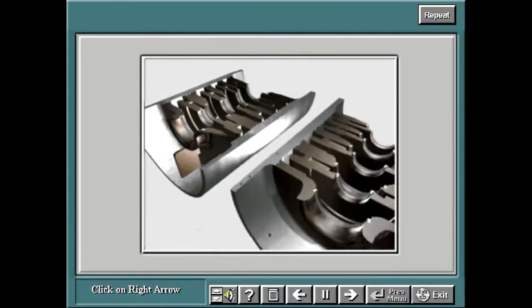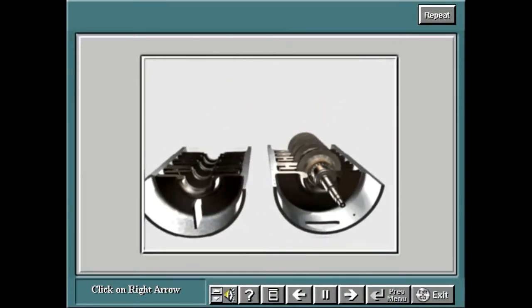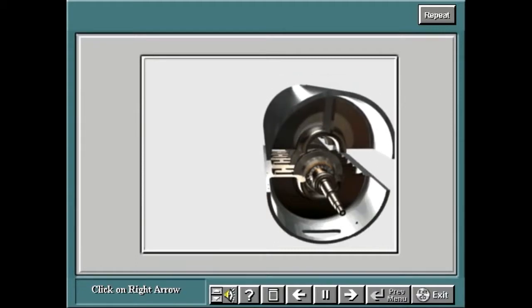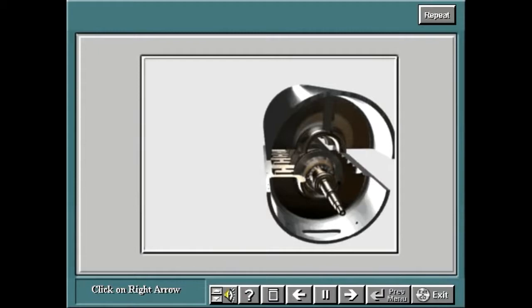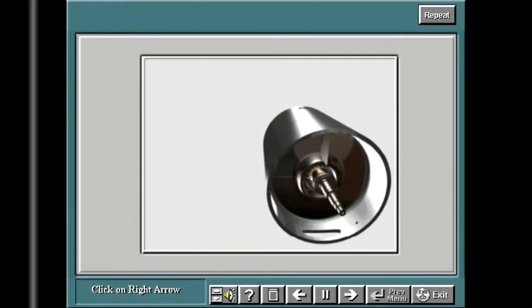The rotor assembly is inserted on the lower half diaphragms and rests on the lower half labyrinth seals. Then the axial position of the rotor is set and recorded. Next, the upper half of the counter casing is placed on top of the installed rotor and lower counter casing half. Before closing the counter casing halves together, O-ring segments, coated with lubricating grease, are fitted into position on the middle split plane of the lower diaphragm to minimize leakage between compression stages. Great care must be taken to ensure a perfect fit between the two halves to avoid internal damage to the rotor and diaphragm.